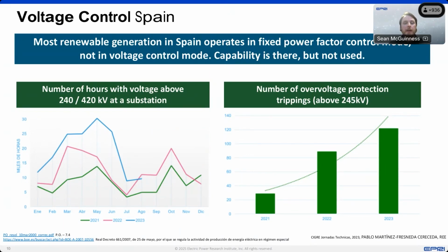Associated with that, there have been a number of trippings of power plants due to over voltages in recent years, and you can see that trend has been rising over the 2021 to 2023 period. Again, we don't want to speculate on what happened last week, but this is more evidence around the challenges that exist on the Spanish grid to actively down-regulate voltage and to provide reactive power control.